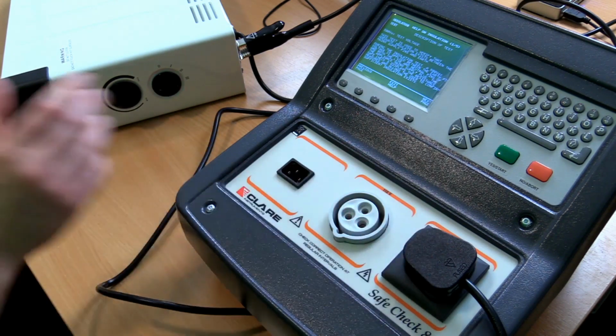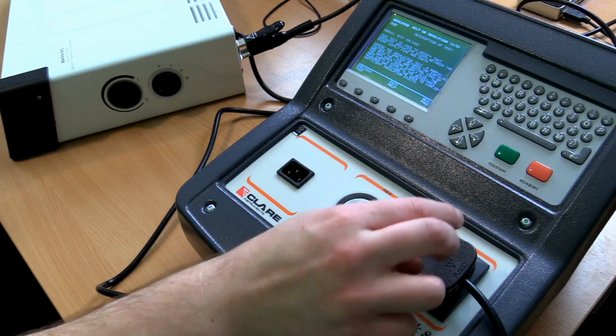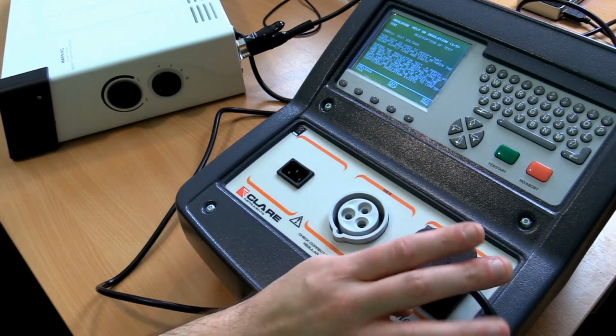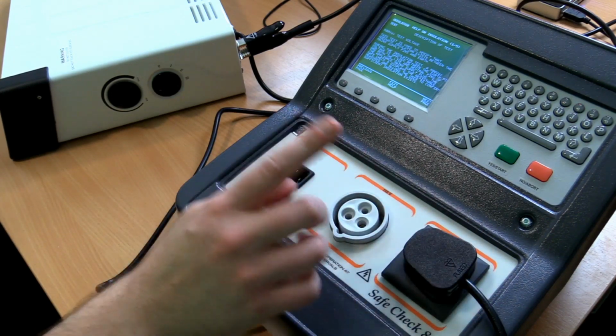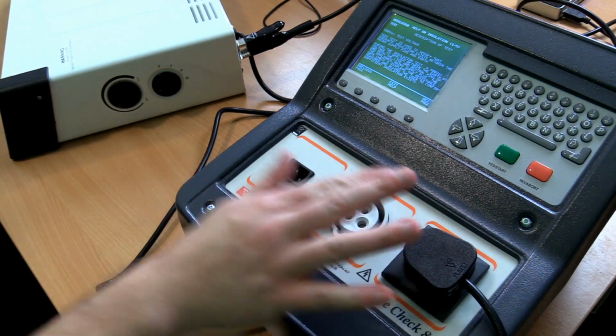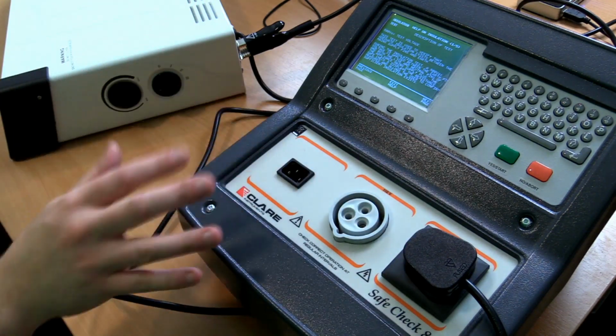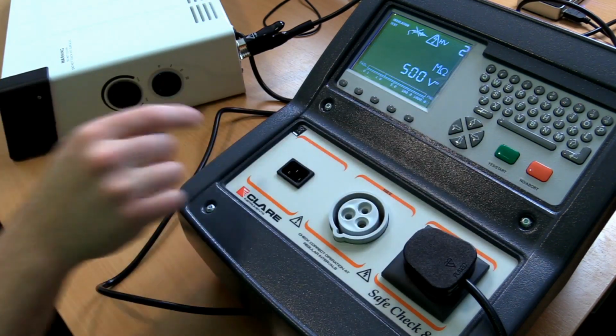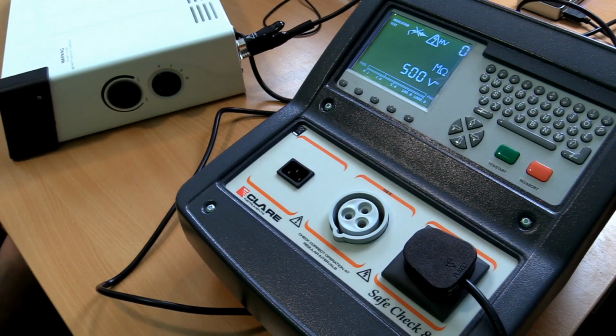So as it's shown in that previous little video, we're going to use live and neutral strapped together, put 500 volts across those, and measure the resistance between those and the metal parts and the earth cable. So I'm going to start this test. We're after a nice high resistance here. And you can see we've got a very high resistance, so that's a pass.